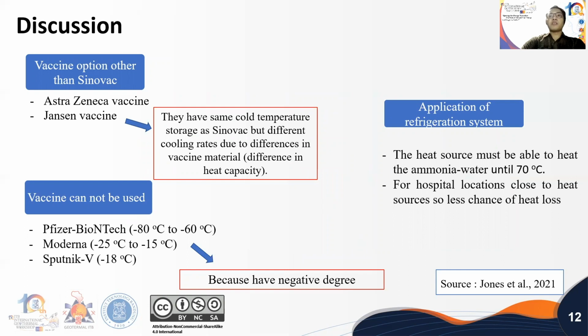In addition to the Sinovac vaccine, this cold storage can also be used for other types of vaccines, such as AstraZeneca and Janssen vaccine. This is because these two types of vaccines have the same storage temperature as Sinovac, but have different cooling rates due to the difference in vaccine material, because of difference in heat capacity. However, this storage cannot be used for vaccine Pfizer, BioNTech, Moderna, Sputnik V, because they have a storage temperature well below the cold storage we designed. We designed 3 degrees Celsius, and the temperature is negative.